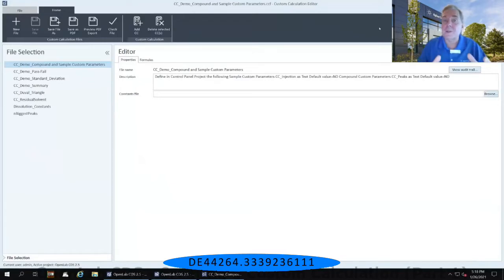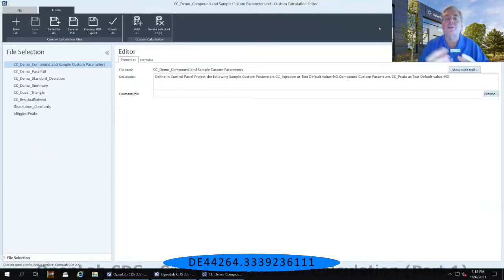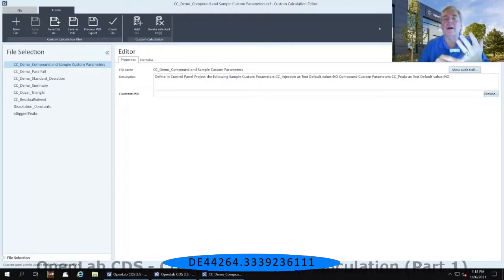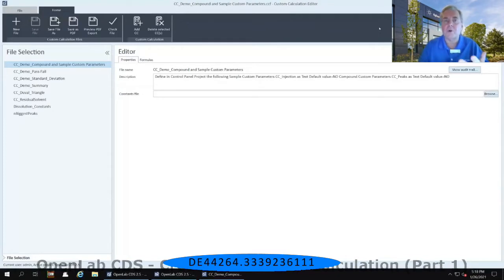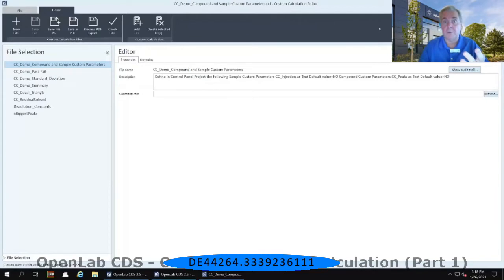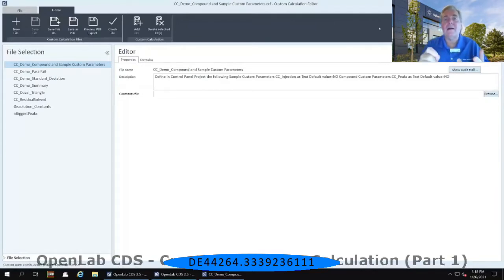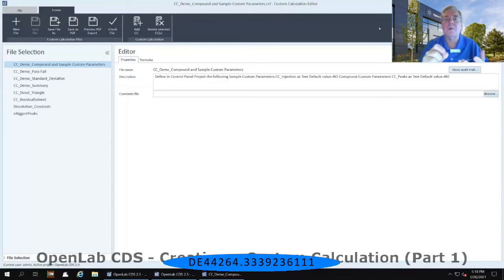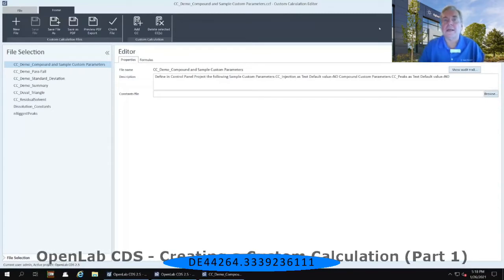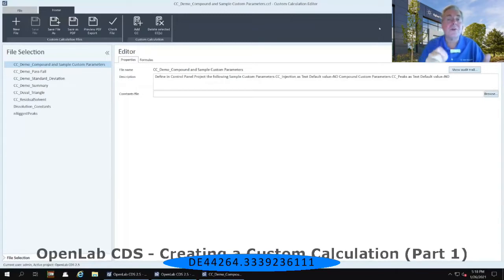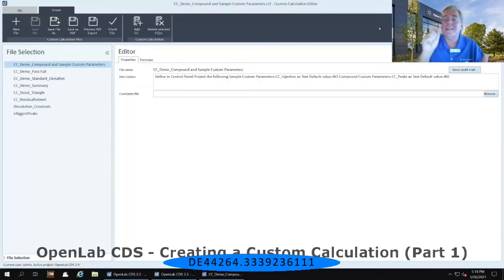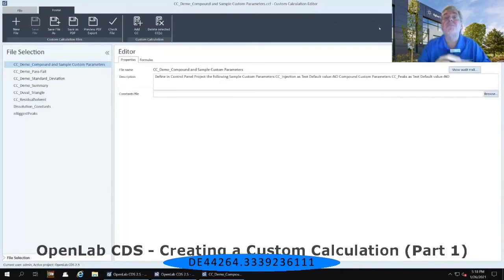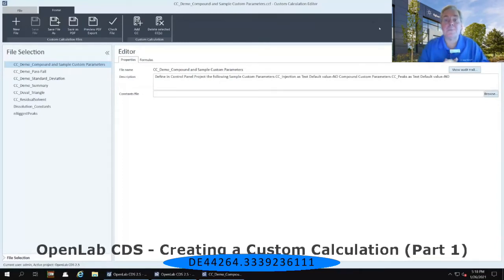For this demonstration, our custom calculation file is going to do two things. I wanted to first show me the area percent of each one of my integrated peaks, so I can see what that area percent is in a column in my result table. Second, I have a USP resolution that's been handed down through my SOP for my QA QC folks that says that my SOP resolution must be greater than 13. If it is not greater than 13, then I have failed that specification.